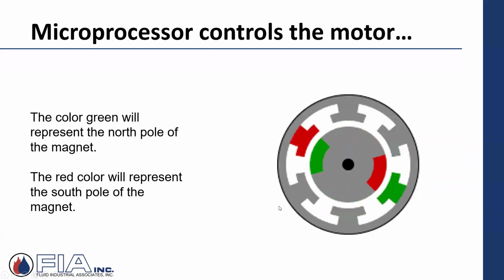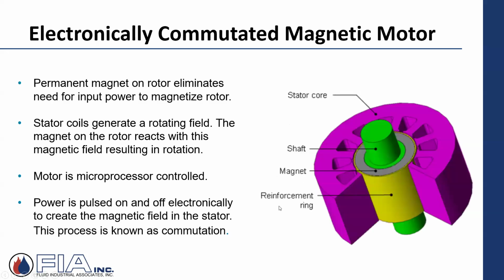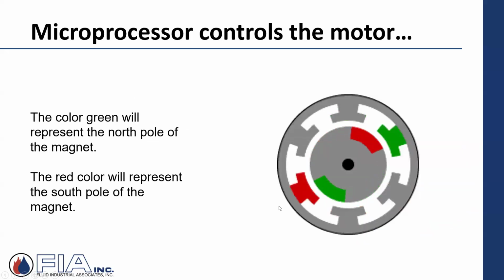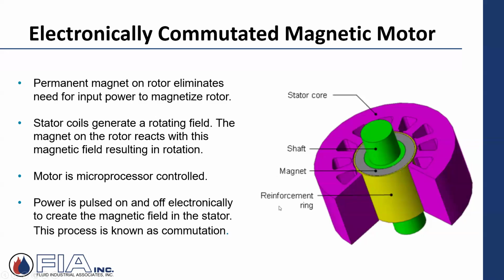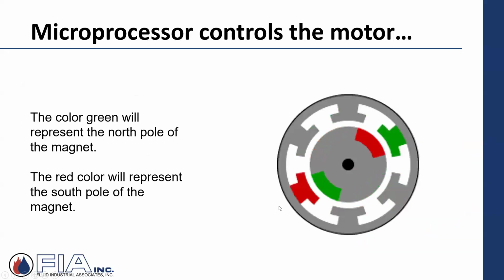So it's a very simple drawing, but what it's trying to show here is the green represents the north, the red represents the south pole. This is my rotor, there's my magnets. That would be kind of this picture here, a rotor with the magnets attached. As I electronically pulse power on and off, and that's what we're saying down here, power is pulsed on and off electronically to create the magnetic field in the stator. The magnets on the rotor react. So opposites. The faster these are pulsed on and off, the faster the rotor spins.